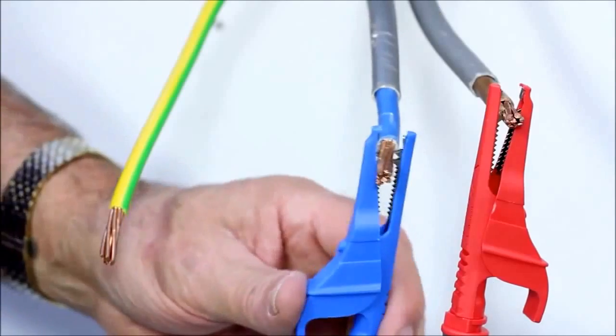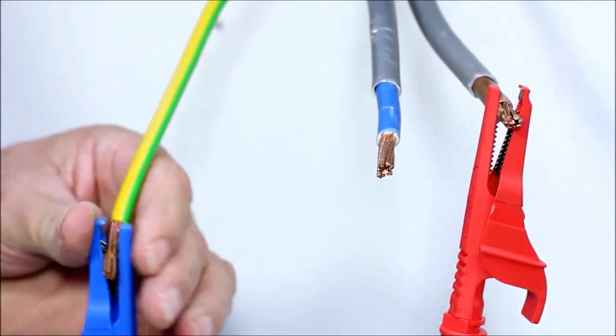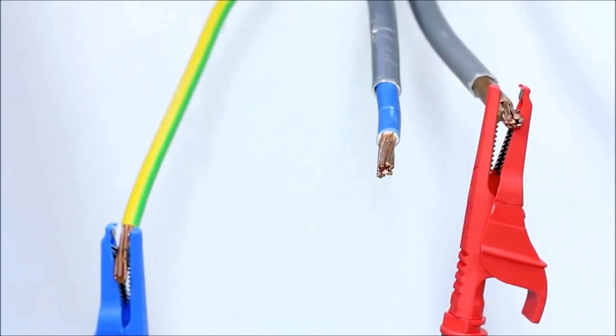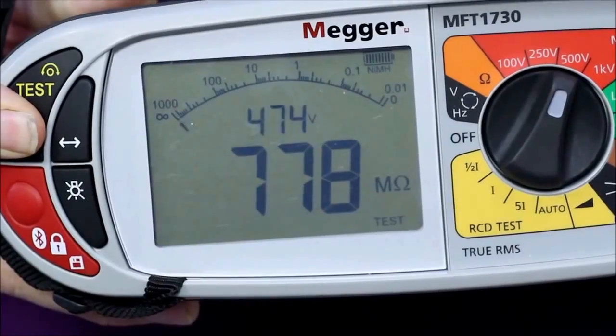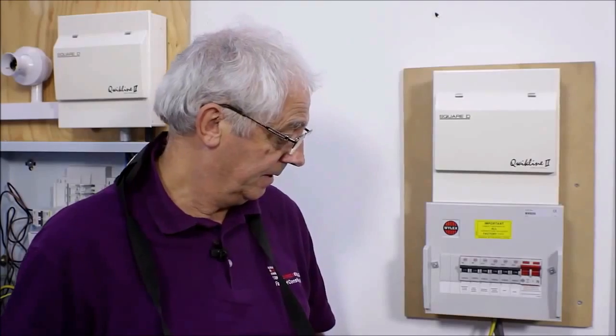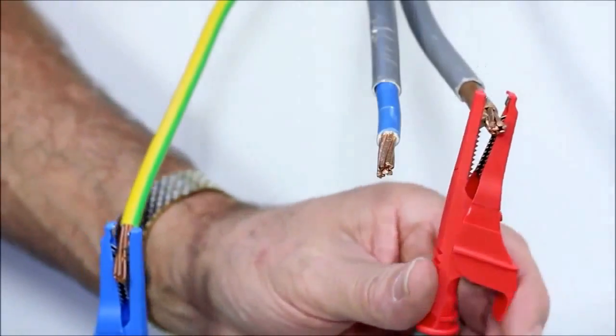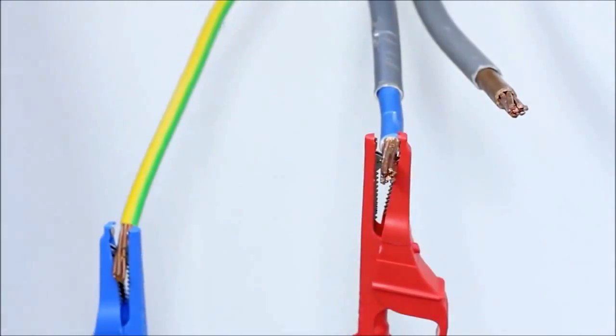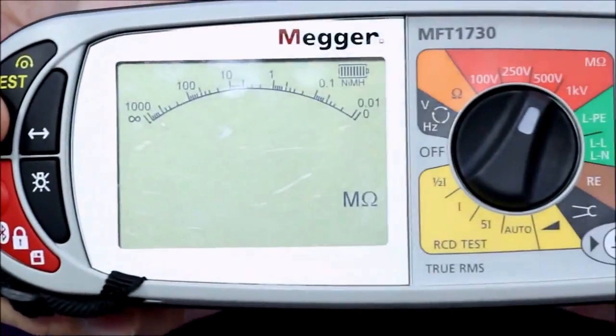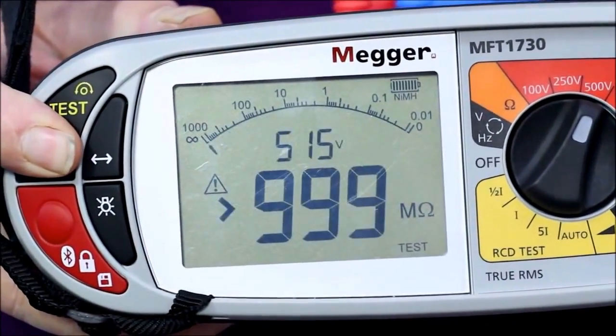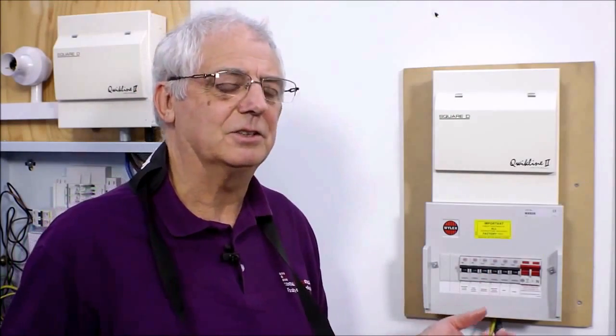Once I've done between live conductors, I'll do a line conductor to earth. Again, push the button, keep it pressed, and I should get a very high reading again. Next part of the test, neutral to earth, push the button, and again a very high reading. And we must also remember that while I'm carrying out these tests, I should go around switching any two-way switches on and off just to make sure that I'm measuring the whole circuit.